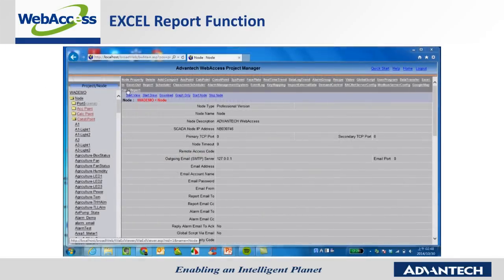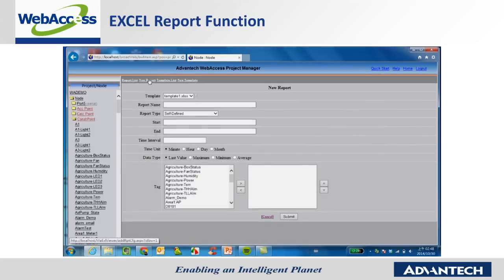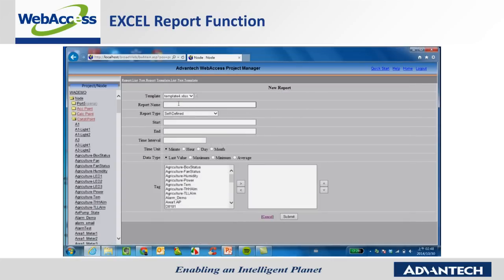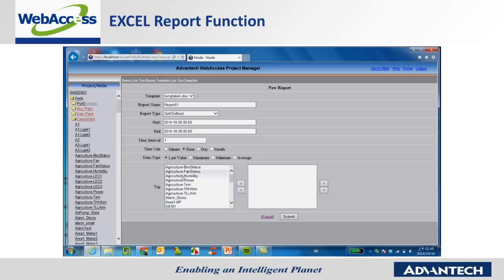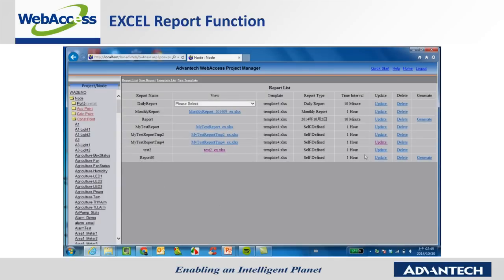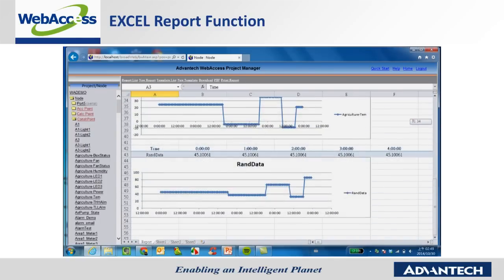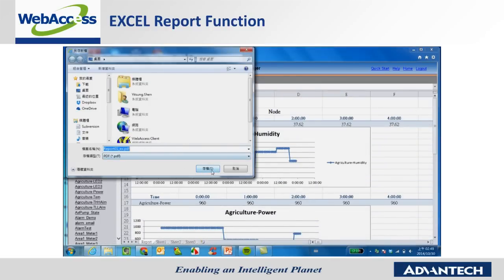Here is a demo of the Excel report function. Choose Excel Report in the Web Access SCADA node and click New Report to create a new Excel report. In the form, configure the report information — choose the template, preview it, type the report name, choose the type of data to report, set the data start time, end time, time interval, and data type. After all settings are done, click Submit and the new report will be added to the report list. Click Generate and the report will show up in Web Access. Users can also download the report as a PDF file and view it on the desktop.